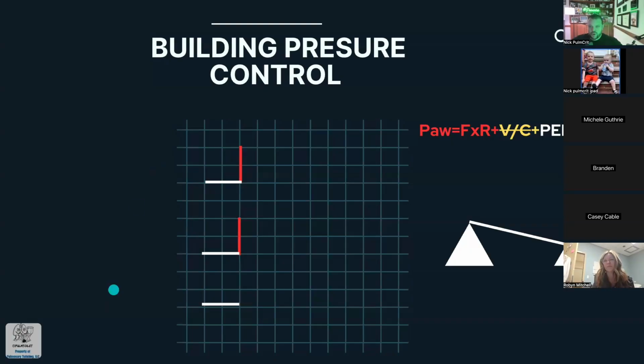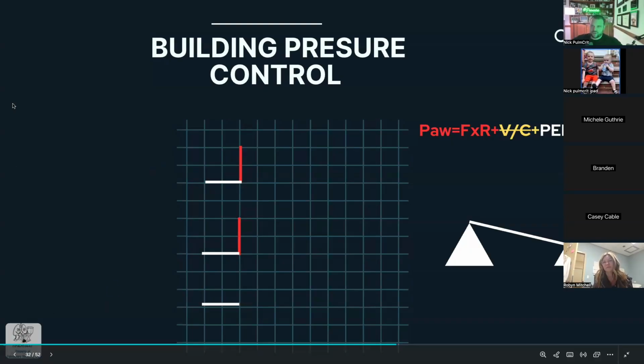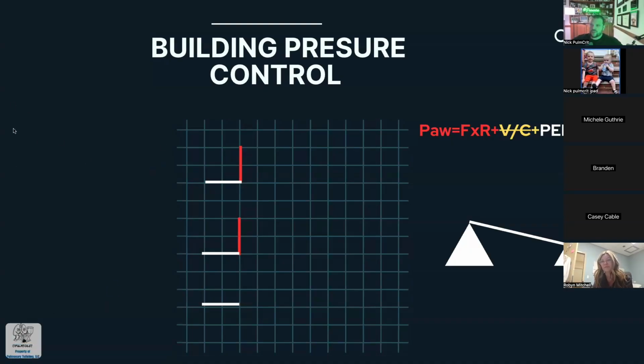Now, important point number 2 or 3, I've lost count. Important point number 2 or 3 is that, remember, in the very beginning of inspiration, at this point, we haven't delivered any volume yet, right? Because we just started inspiration. So your V over C component isn't there. So your pressure here is made up from your flow, your resistance, and your PEEP total. Okay? So we have PEEP here. PEEP is 5.